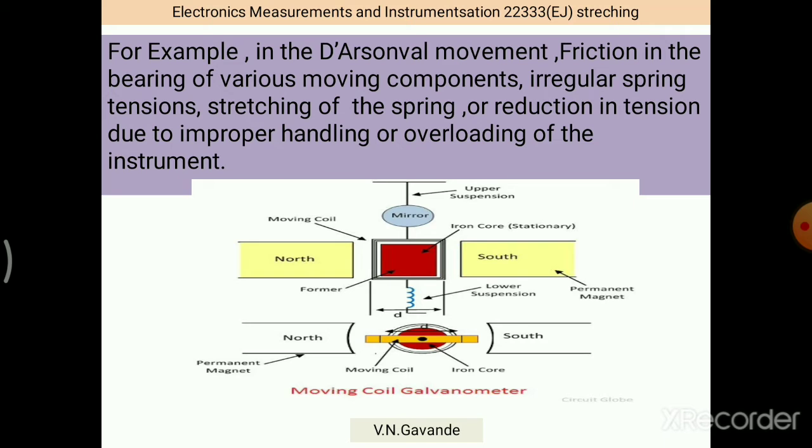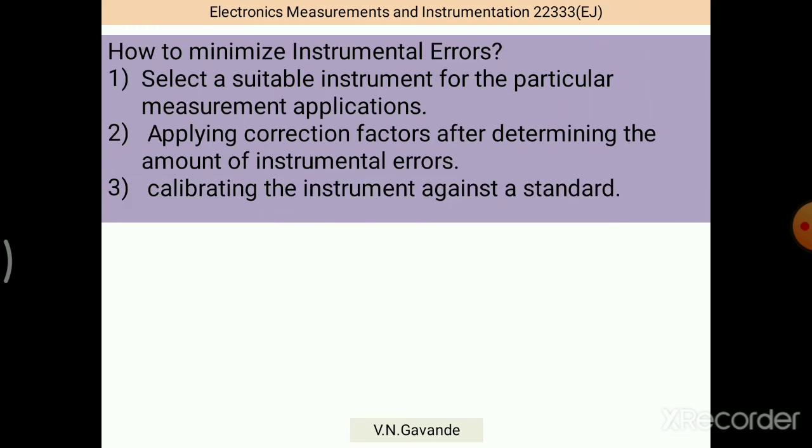For example, in the d'Arsonval movement, friction in the bearings of various moving parts, irregular spring tensions, stretching of the spring or reduction in tension due to improper handling or overloading of the instrument. The picture shows us the moving coil galvanometer. In this case, instead of indicator or pointer, the mirror is used. How to minimize instrumental errors? Very simple. Select a suitable instrument for the particular measurement applications. Applying correction factors after determining the amount of instrumental errors. Calibrating the instrument against the standard.